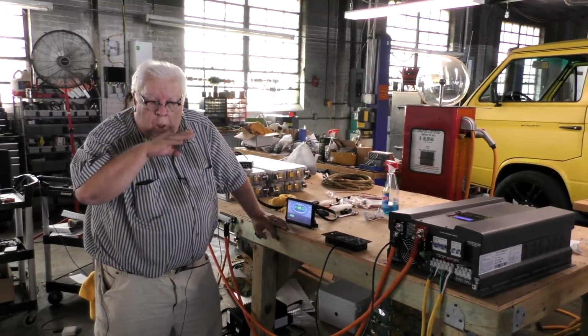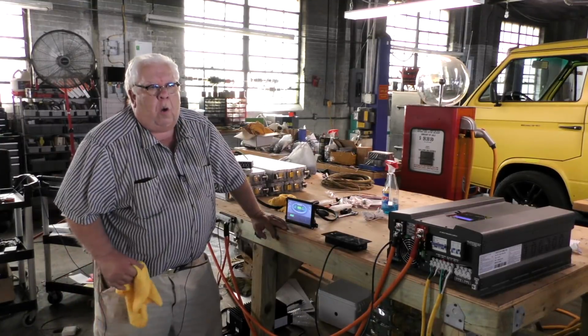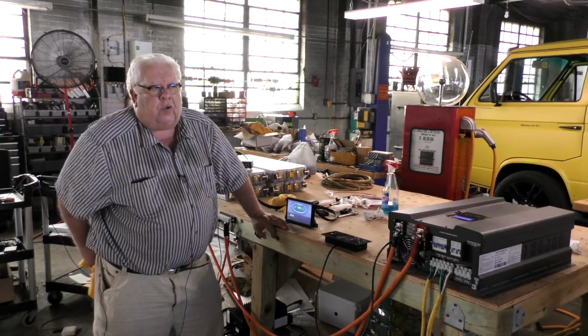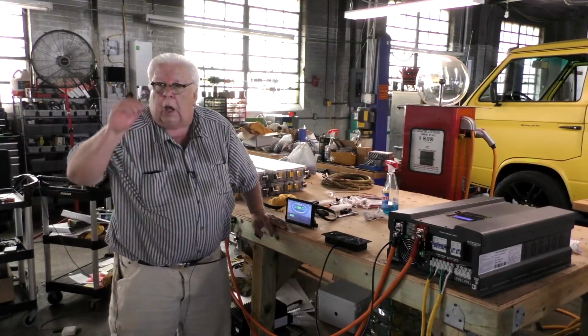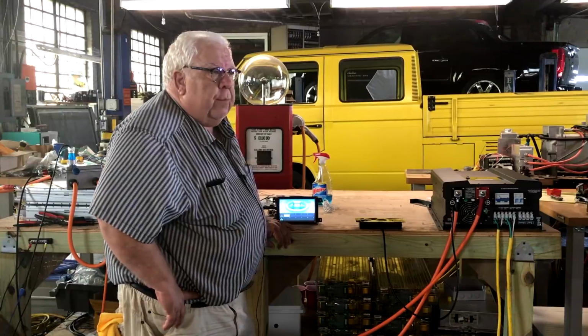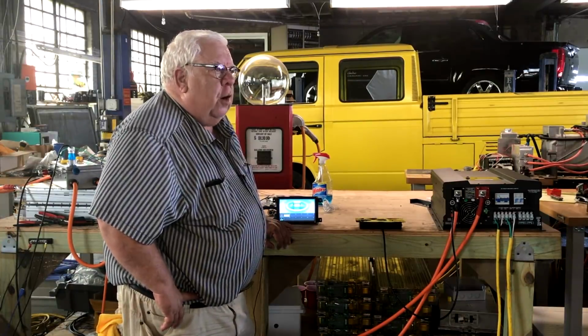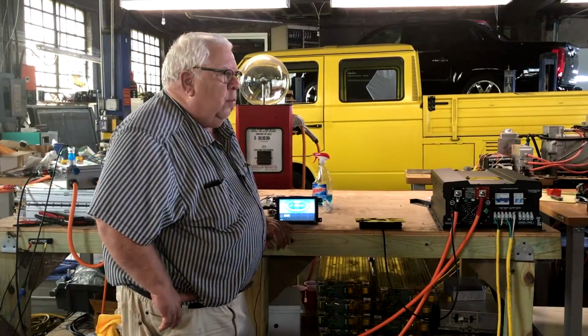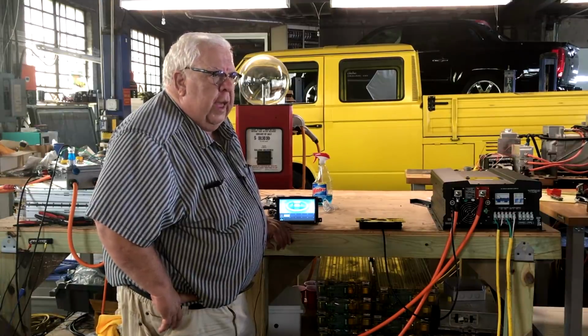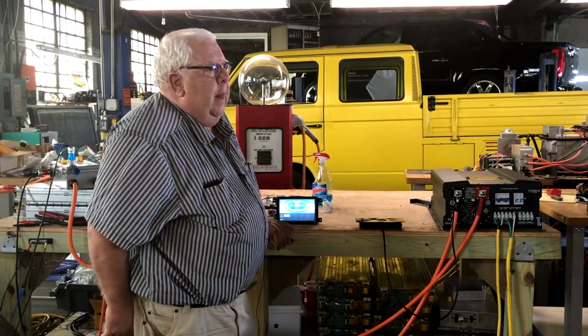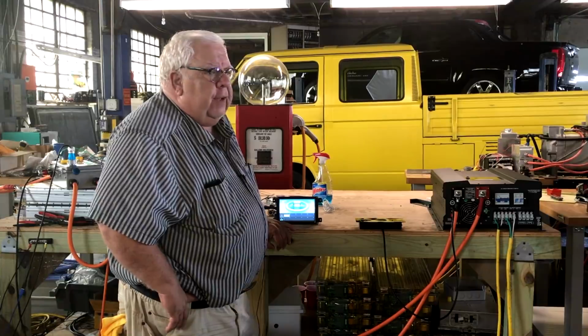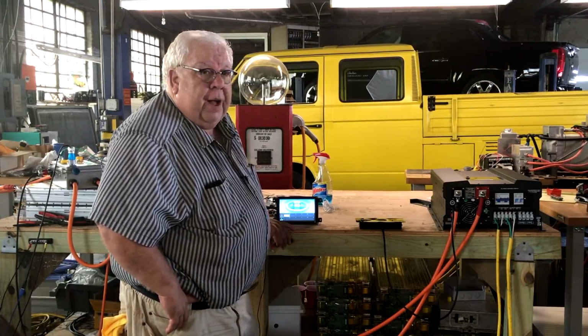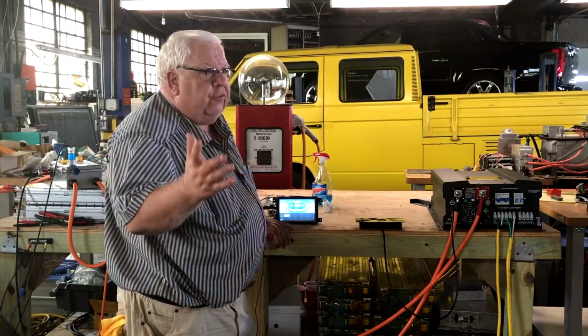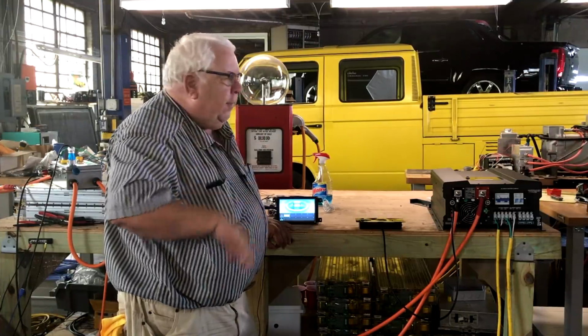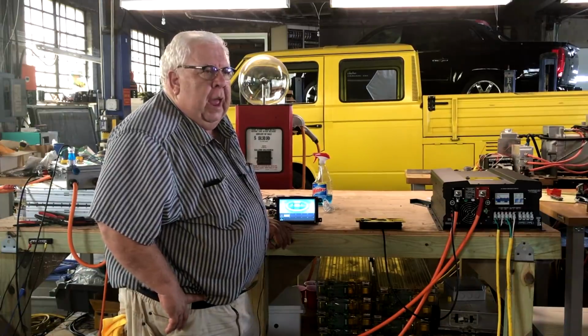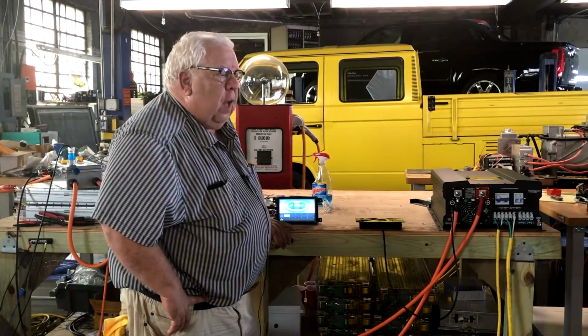We're off the grid. What we've been working on, and I'm very excited about, if you'll recall, a month or so ago, we hooked our grid-tied Solar Edge inverters to a couple of 345 volt transformer-based Chinese inverters, and actually got them to charge the batteries in reverse. I was very curious as to how that would work with a system based on 48 volts. And I understand there's a lot of things that could be done in the control electronics to kill that possibility. There's no reason for them to do it because nobody knows you can do this anyway. But we do. And so I had to get these and test them to see how that would work. And I'm pleased to report it works alarmingly well.